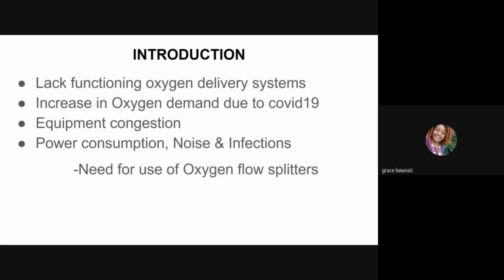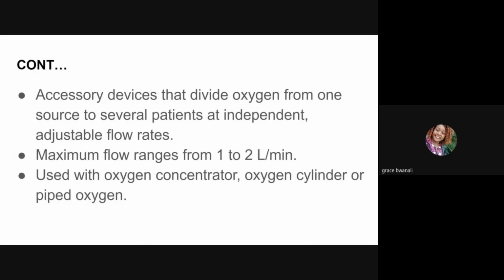As you may note, many health facilities in low and middle income countries have emphasized the shortfalls in oxygen availability. The demand for oxygen is higher than the available functioning oxygen delivery systems due to high population and economic problems. COVID-19 is one of the reasons that led to the increase in demand for oxygen. As such, use of flow splitters ensures a reduction in power consumption, as only a single or few oxygen machines can be powered when there are more patients, like infants, who require oxygen therapy. This is in the case where oxygen concentrators are being used as the source of oxygen. There is also reduced congestion of oxygen devices in the wards when using splitters because only a single oxygen source can be used. Additionally, because there is no movement of oxygen supply when using splitters, some infections may also be prevented. I have mentioned more about flow splitters, but what are flow splitters?